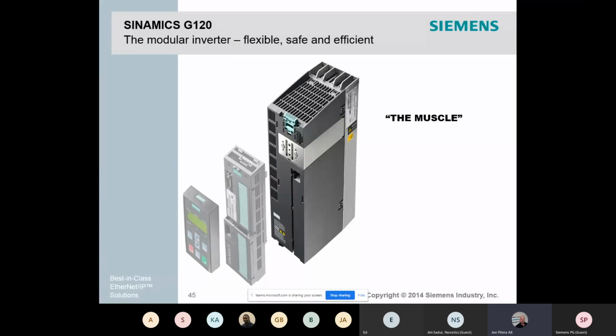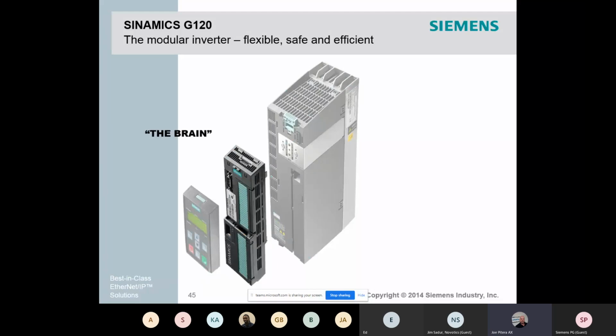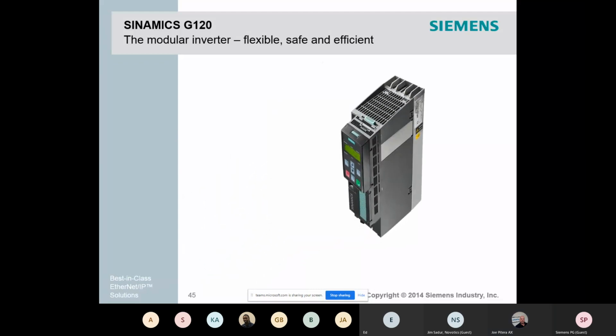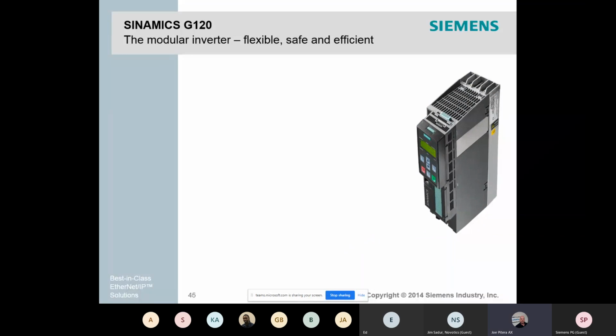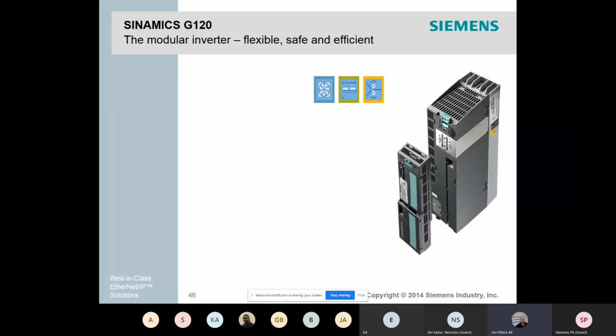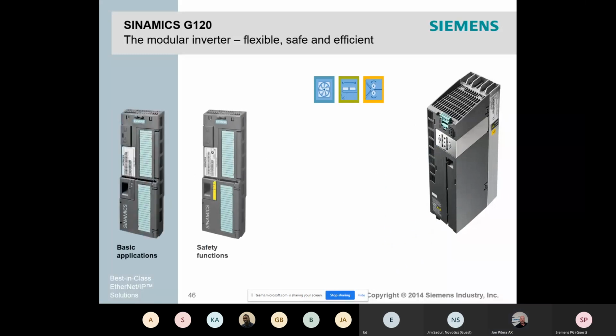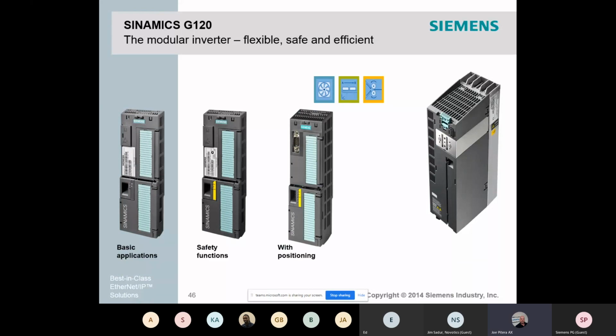The G120 is a modular inverter, more flexible, safe, and efficient. It consists of a power module, or the muscle, a control unit, or the brain, and an operator panel, or the eyes. With the SINAMICS G120 modular system, the inverter can be assembled to match the needs of your machine. You can choose between a control unit for basic applications, with safety functions, or with positioning control. That way, expanding your machine is easier. The same power unit can have different control units that simply clip on and wire in.